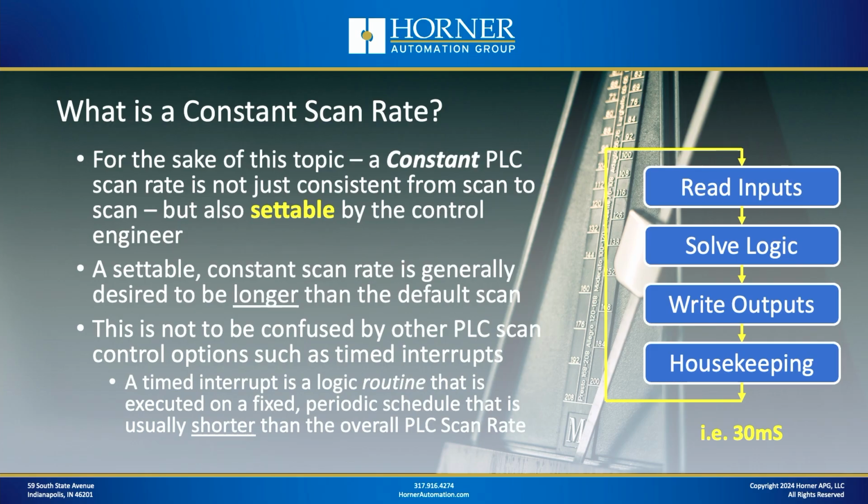And these were really important in the days when PLCs and controllers had really long scan rates. 50 milliseconds was typical, or even 100 milliseconds was typical. And you had a routine you wanted to make sure got executed at least every 10 milliseconds, for instance. So timed interrupts were really important. And again, that ensured that a section of the logic was scanned much faster than the overall logic. That's not what we're talking about today.